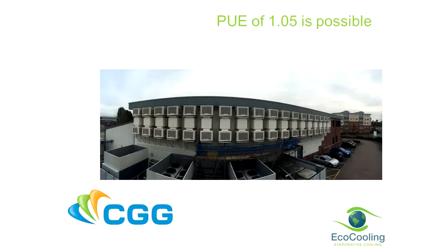This is a data centre down by Redhill. You can drive past this, you go past this in the train. This is a big data processor for the oil and gas industry, about 1.1 megawatt. These guys now are using less than 40 kilowatts to support 1.1 megawatt of cooling.